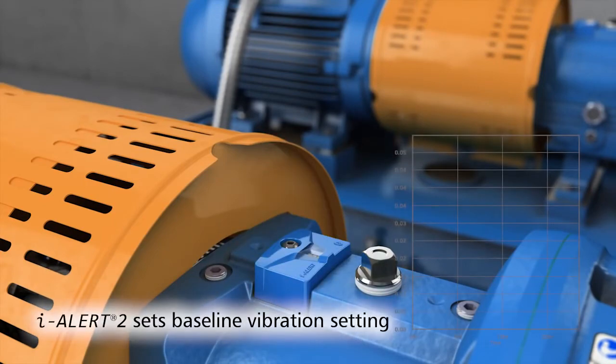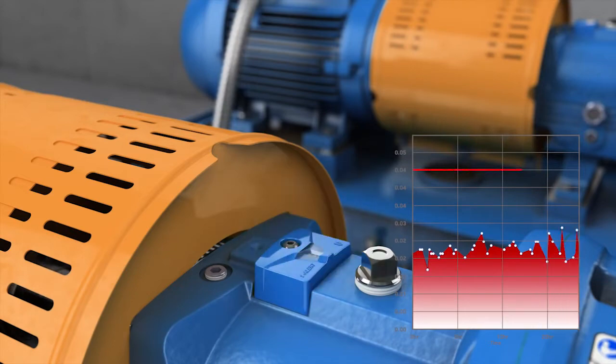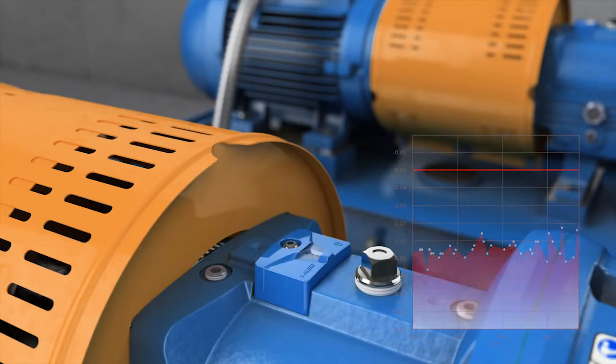When activated, the i-ALERT 2 takes baseline vibration readings for 25 equipment run hours. This baseline is used to set the high vibration alarm levels. No programming is required by the installer.